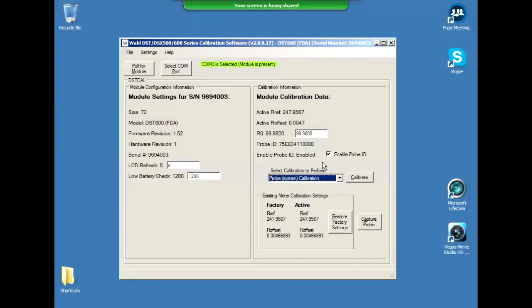But once that's done, that's what these numbers up here are: calibration numbers for the electronics of this specific meter here. R0 is the resistance at 0 degrees Celsius, and when you buy a unit, our probes will be marked with a tag with R0. It also appears on the paperwork, I believe. And what we've done is to adjust out some of the error that's inherent in RTDs. We adjust R0 and set our meter for that. So that basically lets us offset the error that's due to the R0 component of the equation. And I'm not going to go into all that, and you're probably thankful for that. But that's what that does, and that's what we're going to be adjusting here. We'll talk more about that once we do the calibration.